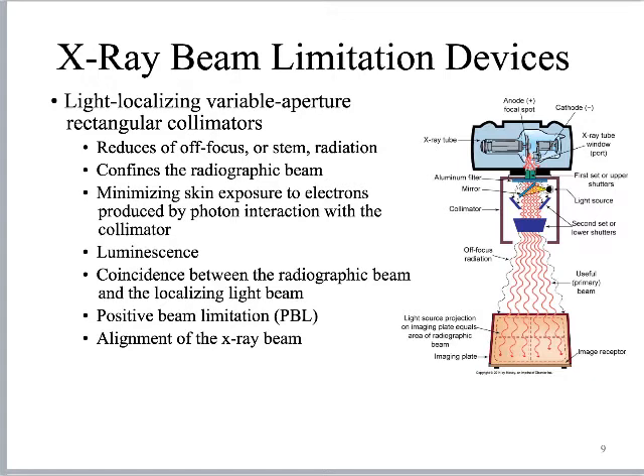The collimated light field should correspond to the area of the actual x-ray beam to within 2%. Positive beam limitation devices (PBLs) are required for all x-ray machines made since around 1980. A PBL automatically limits the light field to match the image receptor size — if you set up for a hand x-ray, the field matches the size of a hand x-ray. Any override to open the field beyond that requires turning a key or disengaging an interlock. I experienced this as a student: I couldn't get the light field to open up because I was at the wrong SID — once I corrected it, everything aligned.